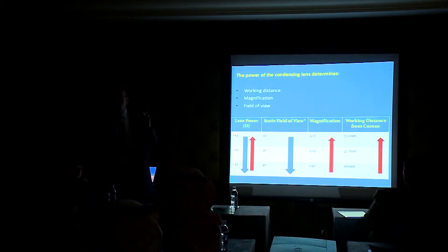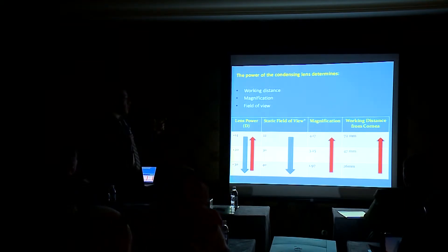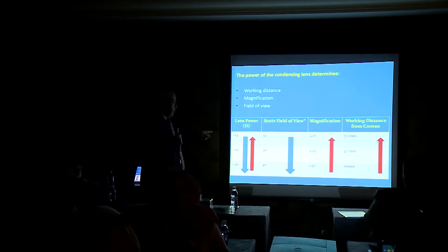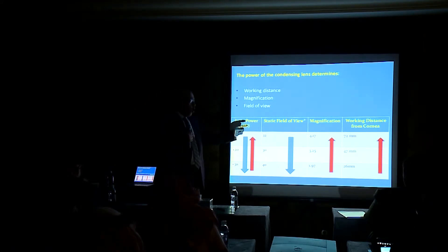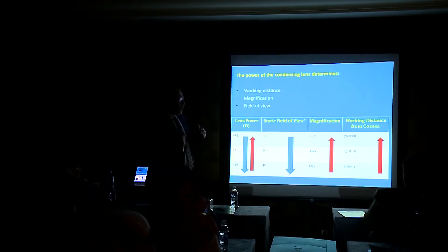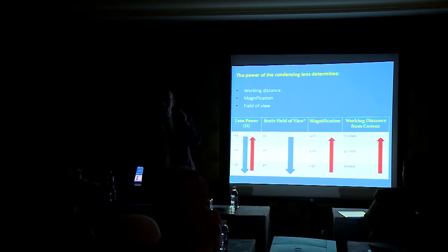The power of condensing lens is very important, so you have to know which lens you are using. If you are using low power lens like the 14 diopters, you get a higher magnification, low field of view, very narrow field of view, and the working distance from the cornea is increased. If you are basic, you use that.